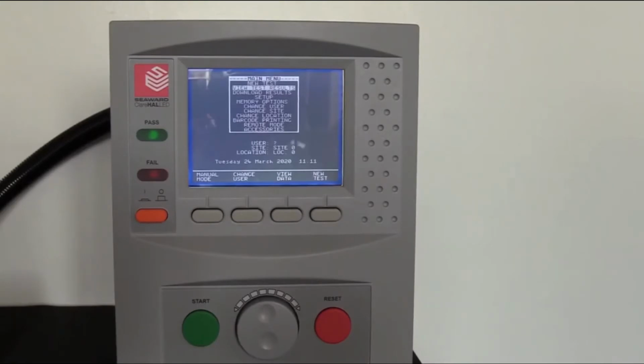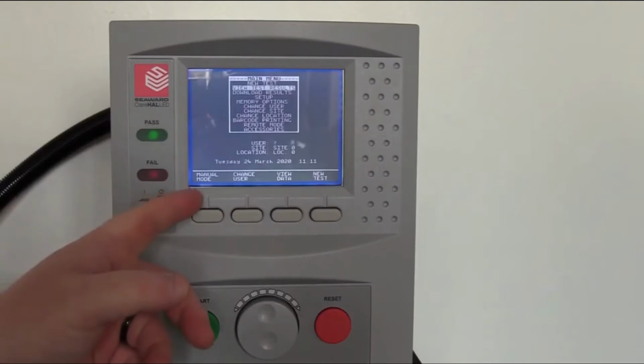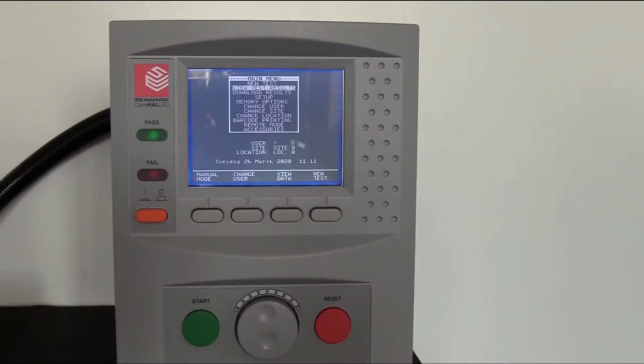There are a number of ways you can perform tests when using the HAL. It can be used in a manual mode, so if you wanted to completely manually perform your tests, for example in a conformance laboratory, then you can do single stage manual tests as often as you need. We can also remote control the unit, so if you did want to set up a piece of software of your own or control the HAL using external software, you can send commands to the HAL, engage it to perform tests and receive responses back regarding test results, etc. But the more common way that this is generally used will be in its own test sequence mode. So that's what we're going to demonstrate and set up for you today.